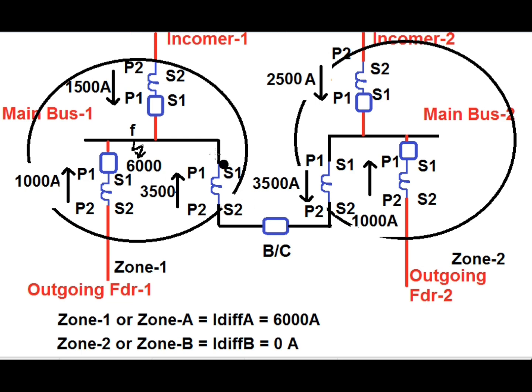The breakers on main bus 1 all trip, isolating the faulty section. For zone 2 or zone B, outgoing feeder 2 has 1000 amperes flowing from P2 to P1, and incomer 2 supplies 2500 amperes from P2 to P1, totaling 3500 amperes towards main bus 2. The current outgoing from main bus 2 towards main bus 1 is 3500 amperes flowing from P1 to P2, which is exactly opposite to the sum of the incoming currents. Therefore the zone 2 or zone B differential current is zero, and zone 2 remains under stable condition.